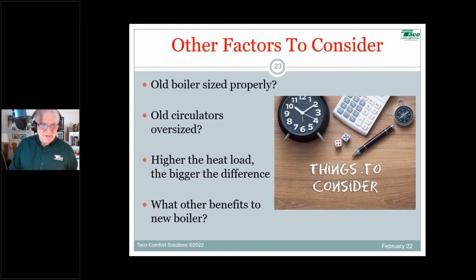Why do we not factor in emitters and potential water temperature drop with a 95% boiler? Well, you kind of do, it's kind of in there. Math-wise it's hard to figure out because each boiler is set up differently for different applications. But you can make a blanket statement, Zach: a low temperature application, where that boiler is in the 120s at max in the dead of winter and goes lower as it gets warmer, is going to be more efficient than setting up a ModCon boiler to make 170 or 180 degree water under design conditions and then resetting. I forget the exact math, but I recall for every 3 degrees you lower water temperature, you gain 1% in efficiency. That sticks in my head, though I'm not sure exactly how accurate it is.